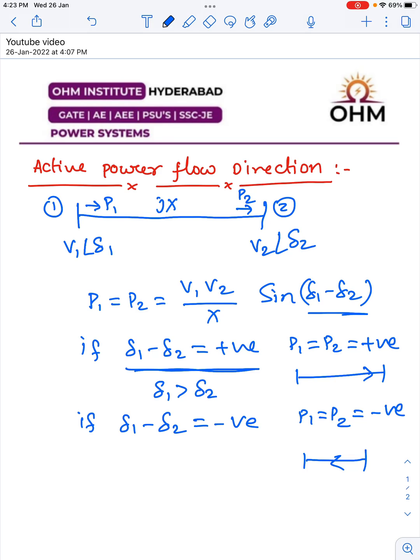The final conclusions are: First, active power flow always depends on the load angle difference between the buses. Second, active power always flows from the higher load angle bus to the lower load angle bus.